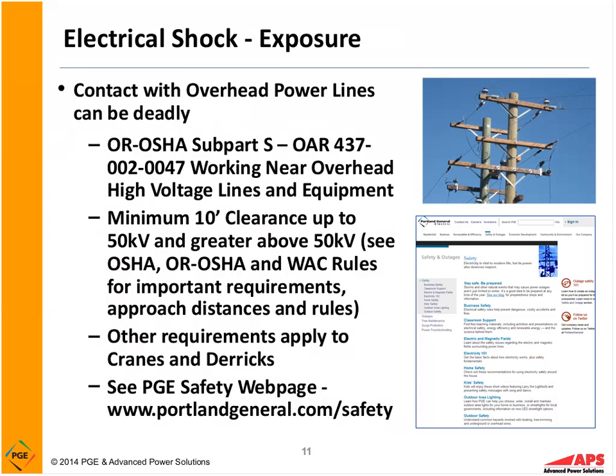So we also have overhead lines. Contact with overhead power lines can be deadly, and it doesn't even take direct contact. Even getting close enough to the overhead lines, there is enough voltage on many of these lines that it will find you. If you get close enough to the lines, it will arc over to you. So we have Oregon OSHA Subpart S and the Oregon Administrative Rule 437-002-0047, working near energized overhead lines, which deals with what we call working clearances. They talk about the minimum working clearances, and the minimum they're calling for is a 10-foot clearance up to 50,000 volts and greater clearance above 50,000 volts.